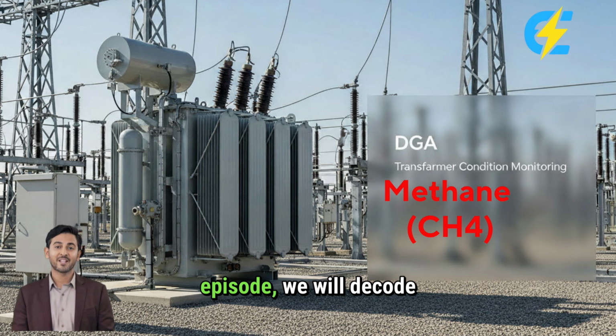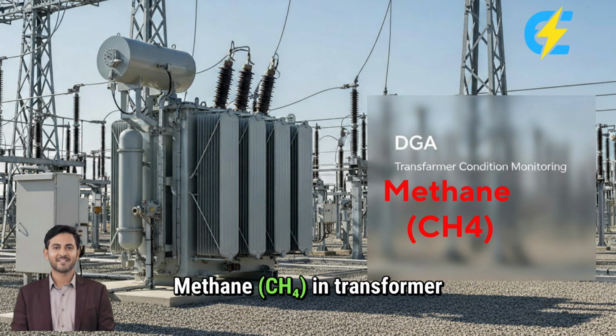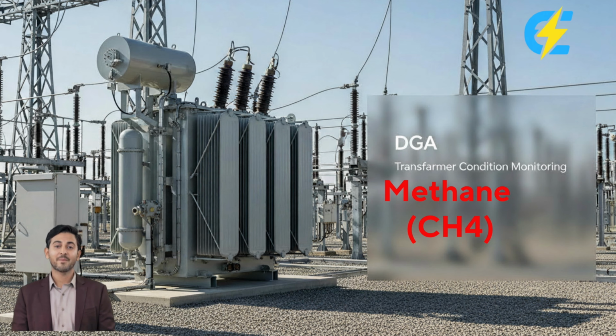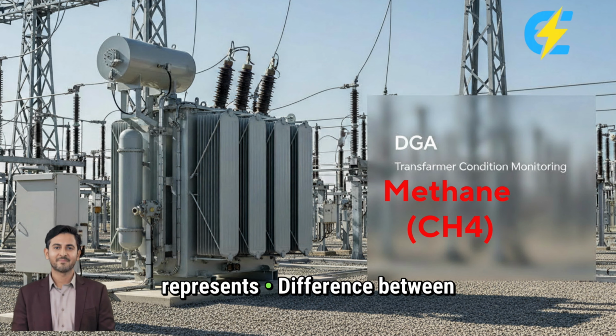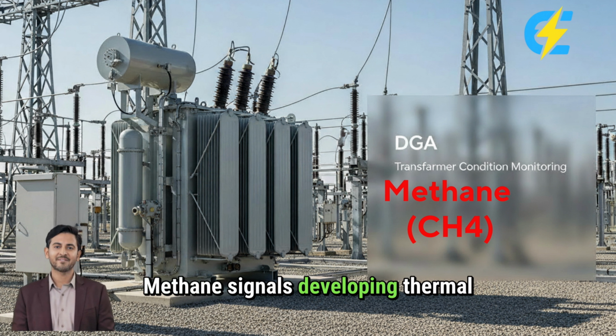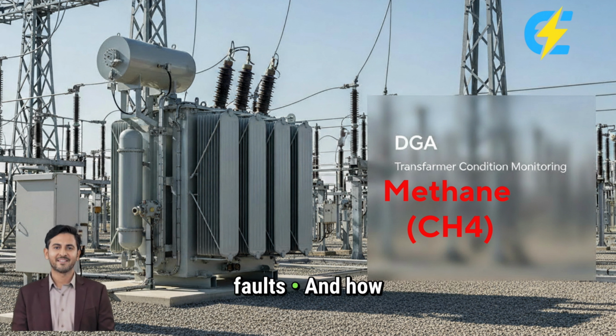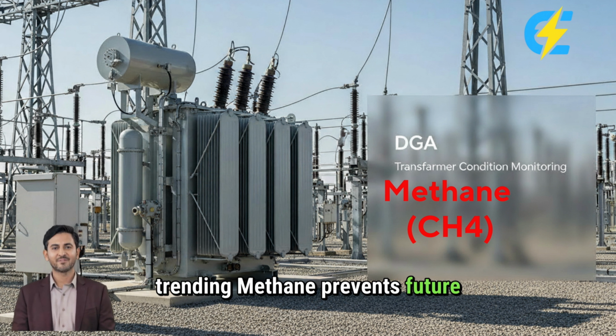In today's Electroverse episode, we will decode methane, CH₄, in transformer DGA. Why methane is generated inside transformer oil. What temperature range it truly represents. Difference between hydrogen only versus hydrogen plus methane. When methane is acceptable. When methane signals developing thermal faults. And how trending methane prevents future failures.